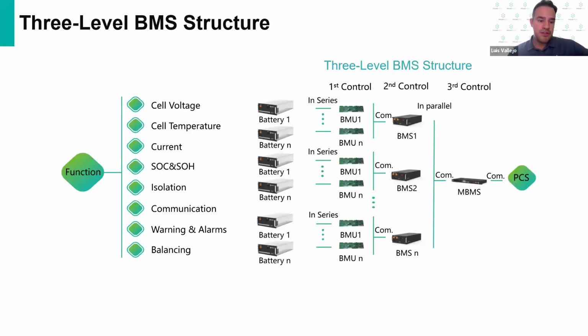This battery system features three levels of BMS structure: the BMU, BMS, and main BMS. This ensures optimal performance by monitoring key parameters like cell voltage, cell temperature, and SOC of the cell. Each battery has a BMU inside, which regulates and controls the battery. The second level is the BMS, which controls the whole string of batteries and ensures proper communication between the slaves and the master battery. Finally, the main BMS collects all the BMS information and communicates it to the PCS and/or the EMS for good cooperation and better operation performance.